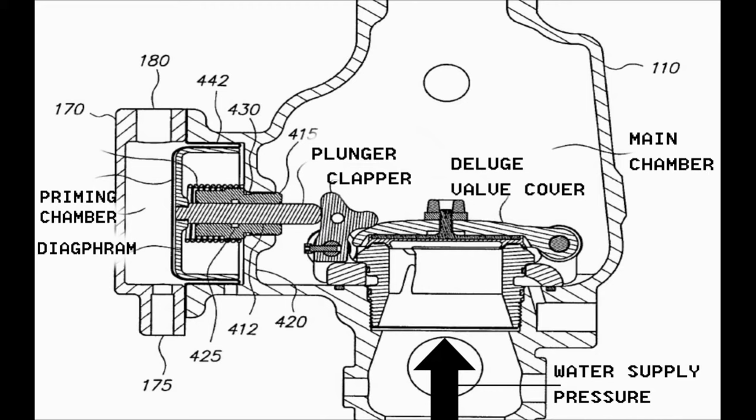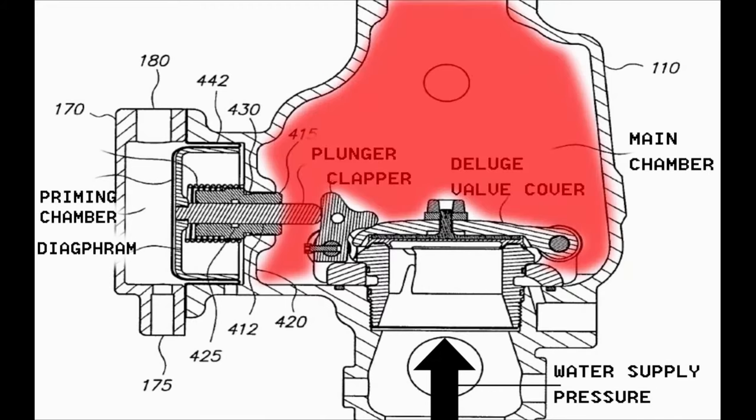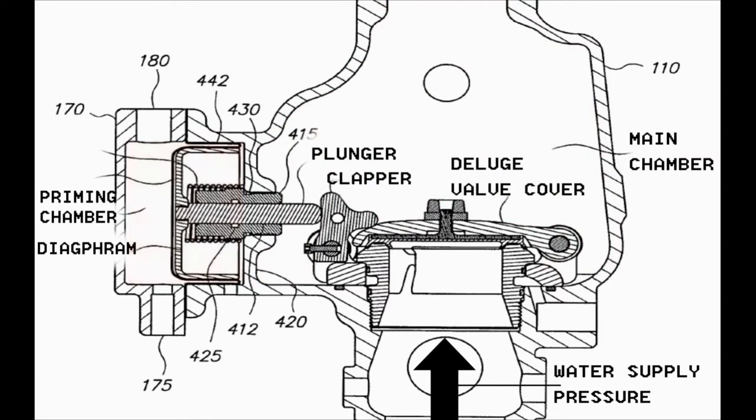The deluge valve consists of two chambers: a main chamber, in which there is the motion of opening and closing the deluge valve, and a priming chamber — also referred to as the sensing chamber — in which there is the motion of the diaphragm responsible for opening and closing the deluge valve. The position of the deluge valve depends on the differential pressure between the priming chamber water pressure and the water supply pressure.